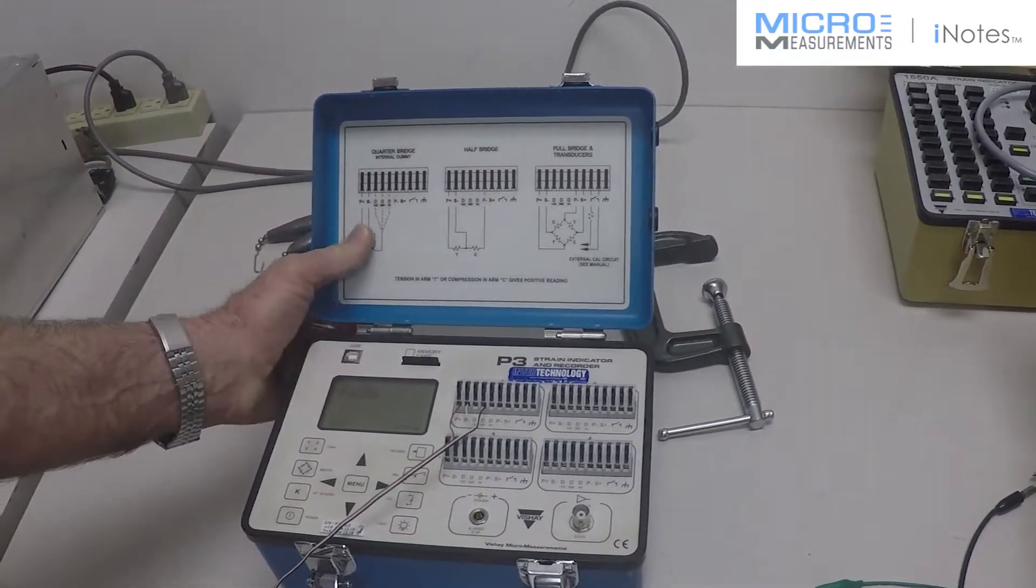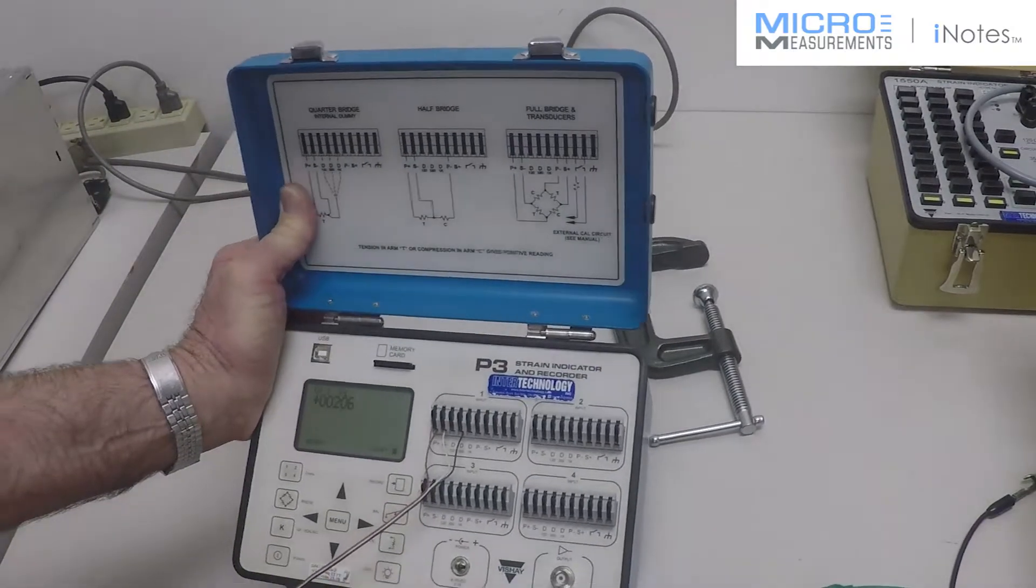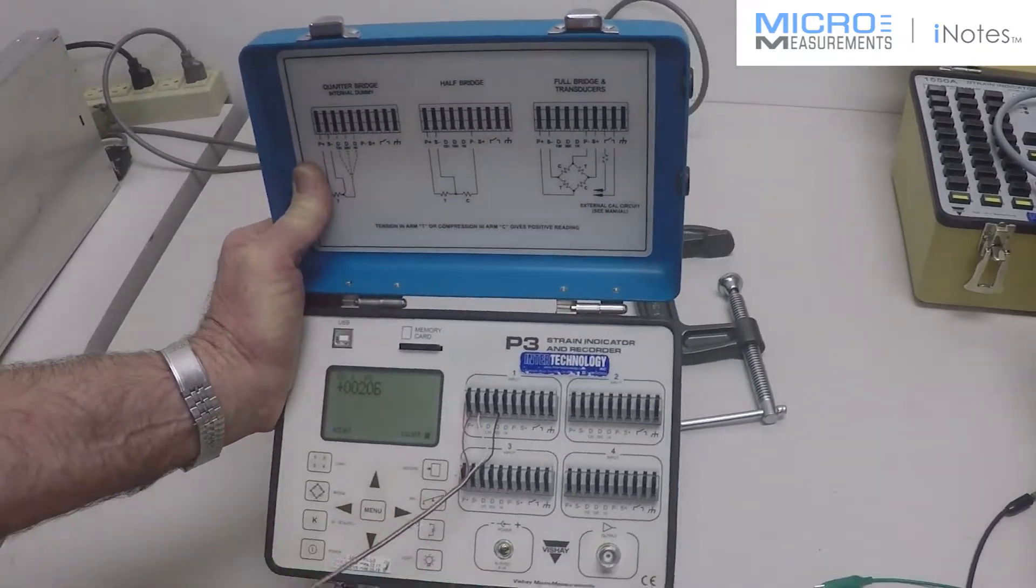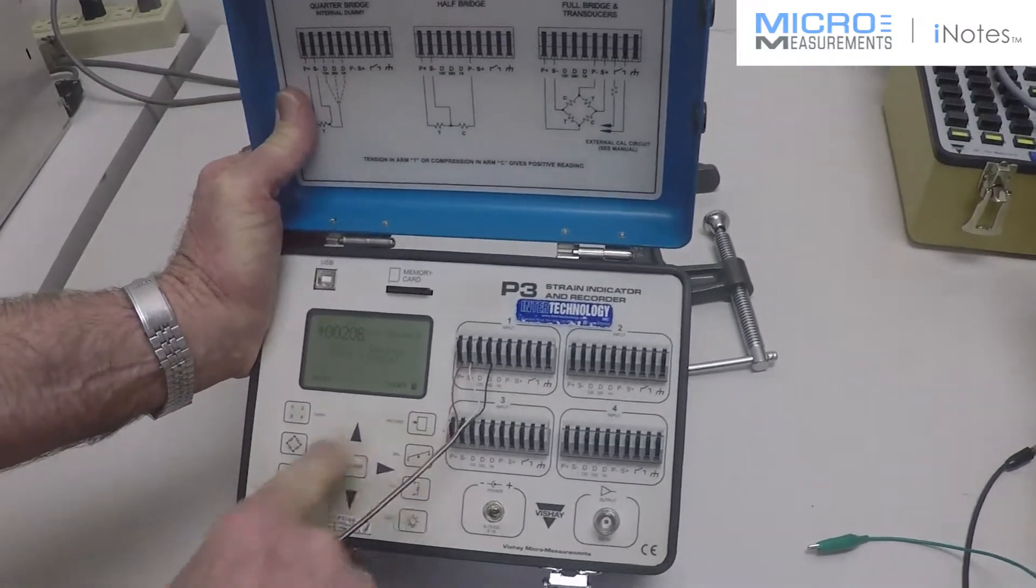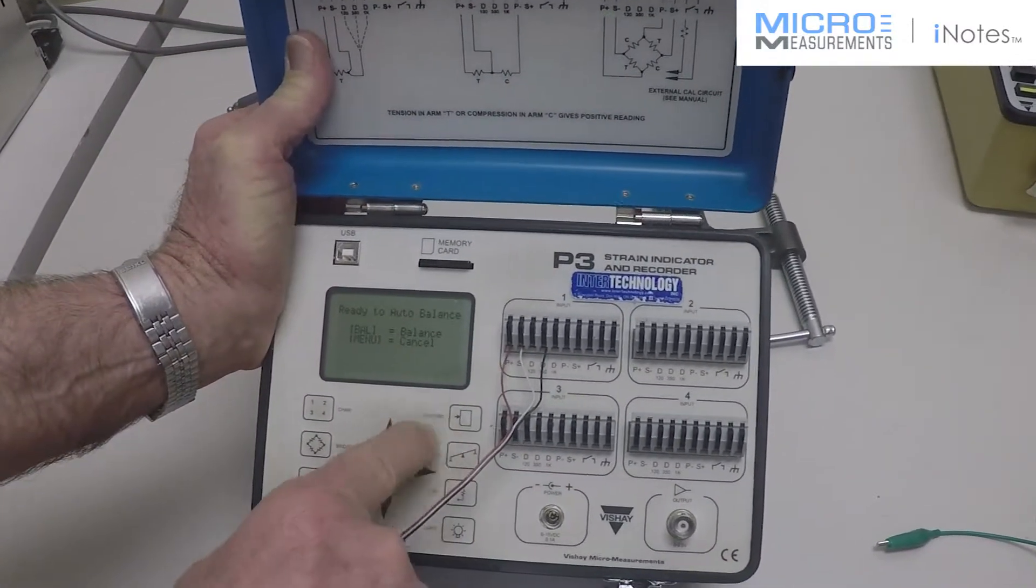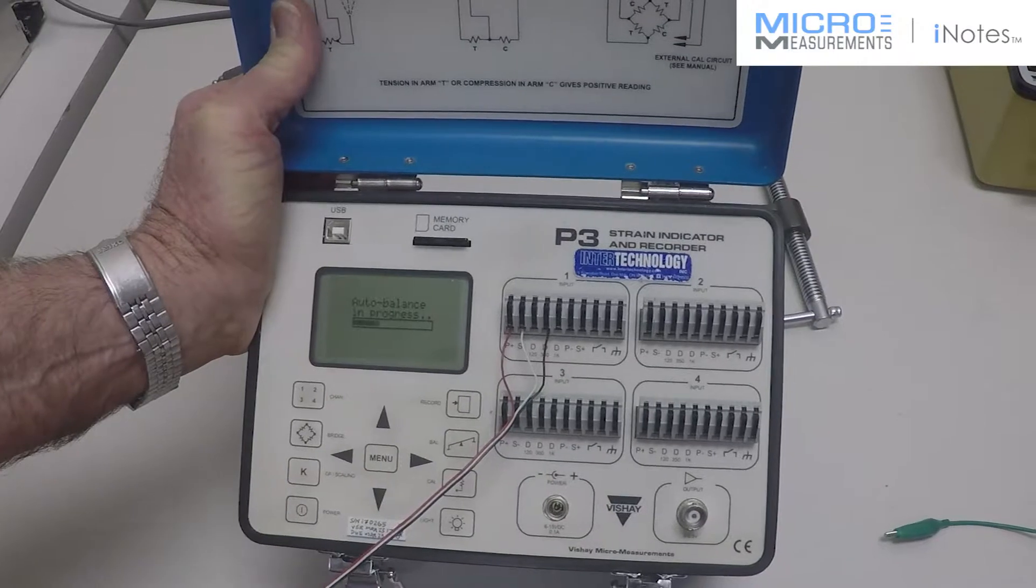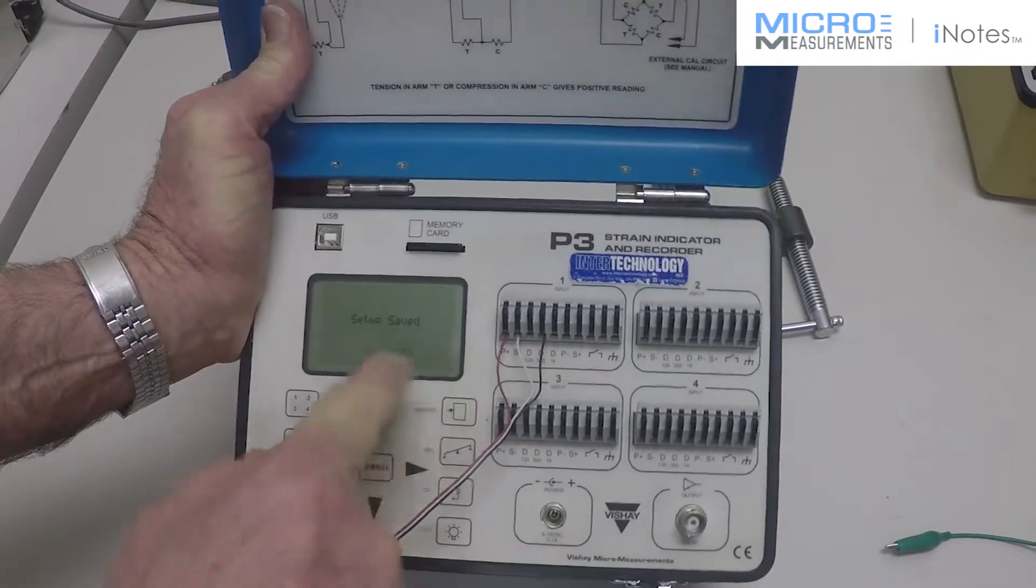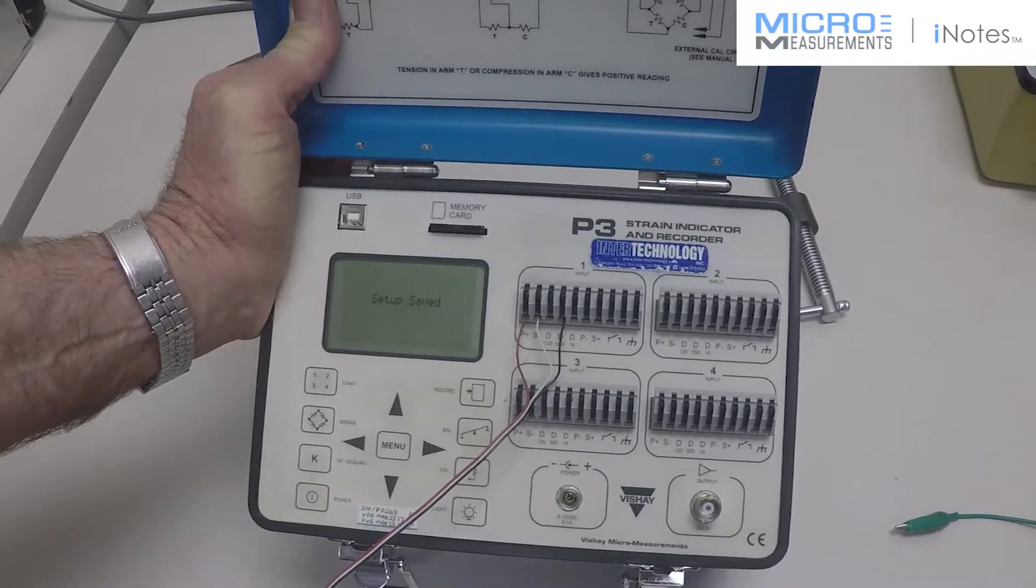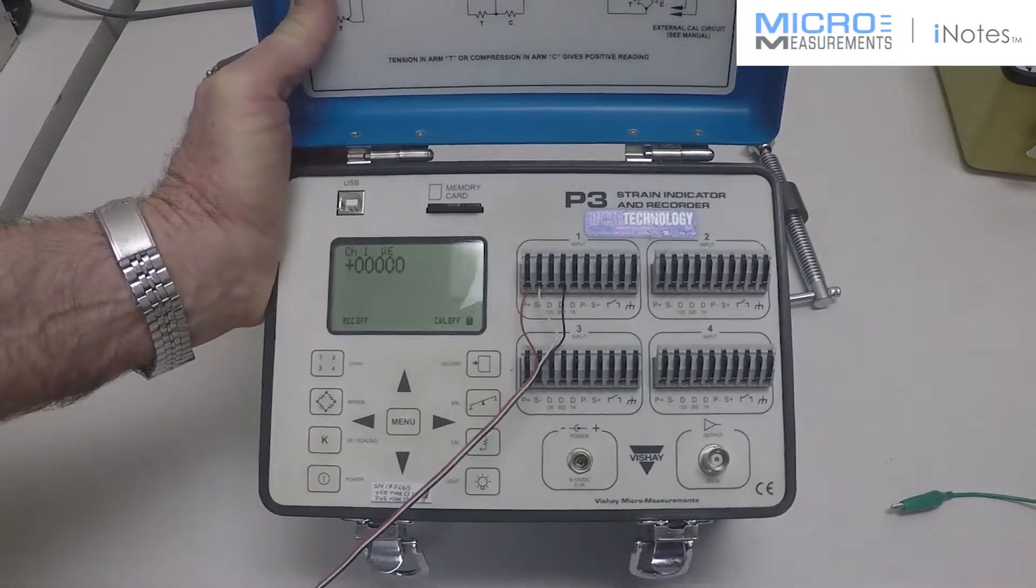We also have, very importantly, the ability to balance the bridge to zero with no load on it. So we're going to press balance over here, and we press balance again it'll automatically balance, and I will save the setup and the balance condition, and we end up with a zero count.